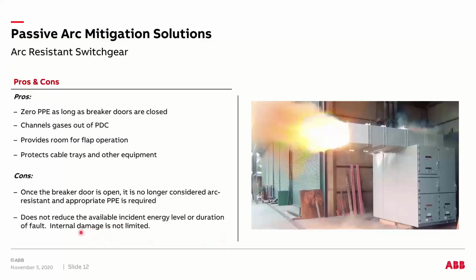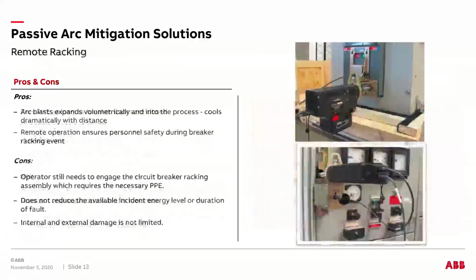But you do not limit the amount of incident energy level that is occurring inside the equipment. On the front, definitely you have a category 1. There is no category 0 now. So it's a category 1 PPE for an arc resistant equipment, but there is some significant damage within your equipment for an arc resistant switchgear.